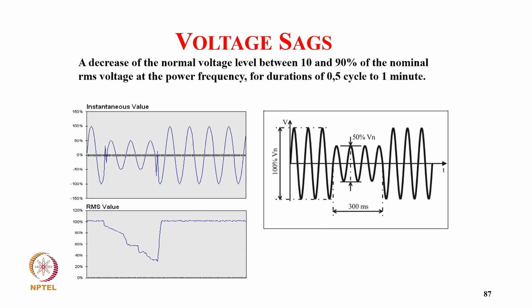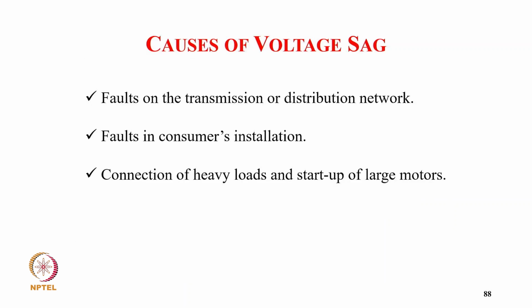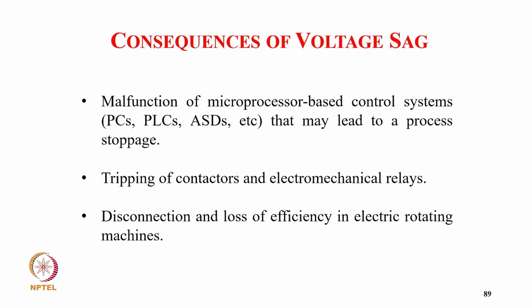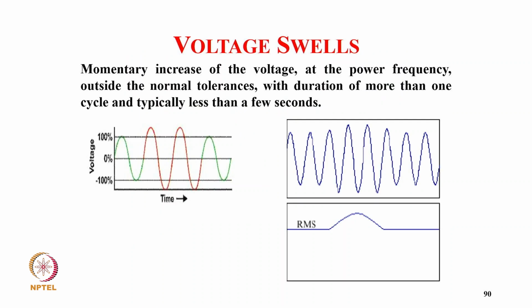A voltage sag is a decrease in the normal voltage level from 10 to 90% of nominal voltage at power frequency for a duration of 0.5 cycle to 1 minute, as you can see here with the different values. The causes of voltage sag are faults on the transmission or distribution system, faults in consumer installations, connection of heavy loads, and startup of large motor loads. Consequences of voltage sag: malfunction of microprocessor based control systems, PCs, PLCs, ASDs, which may lead to process stoppage, tripping of contactors and electromechanical relays, and disconnection and loss of efficiency in electrical rotating machines.